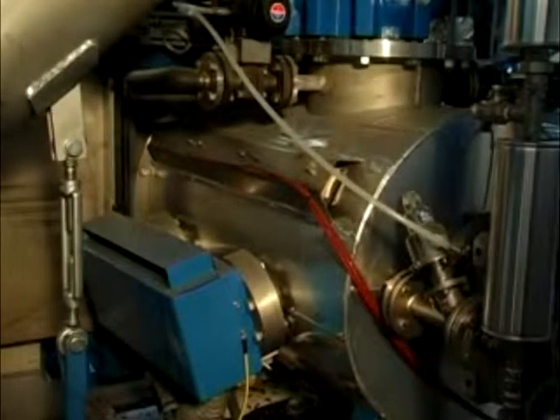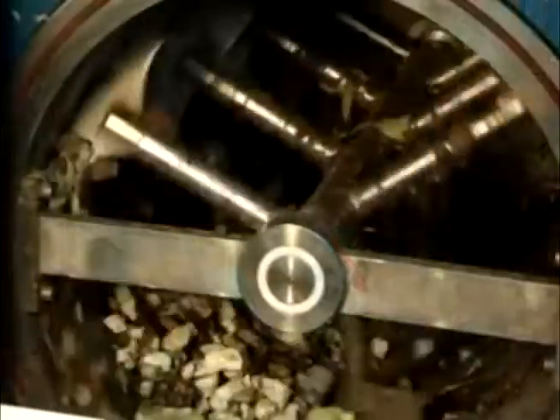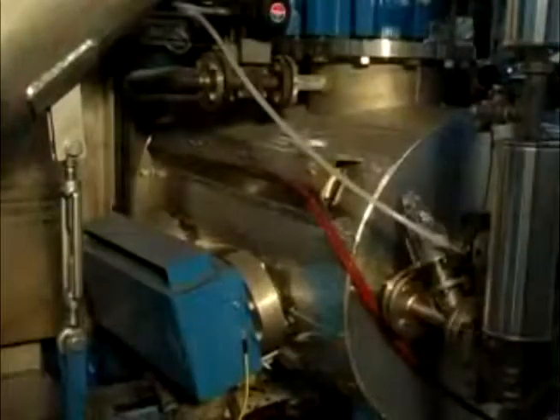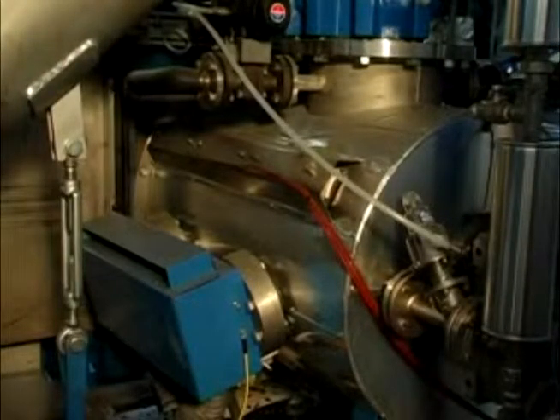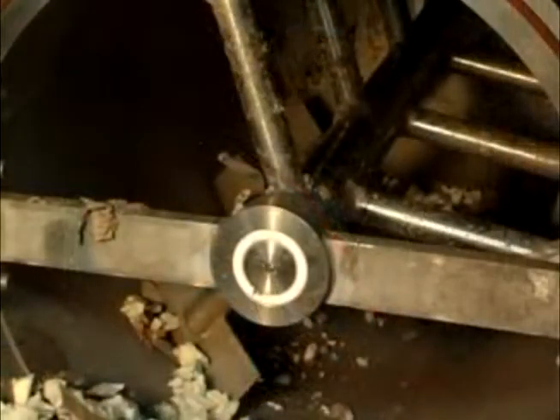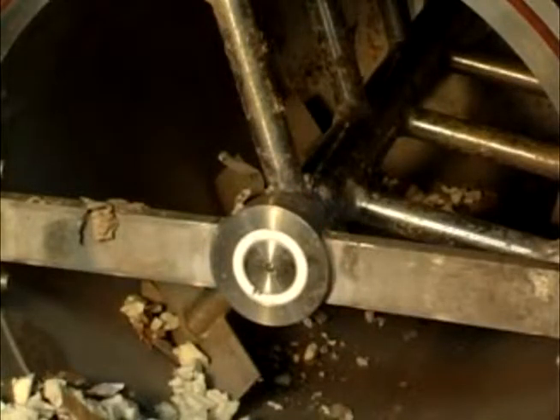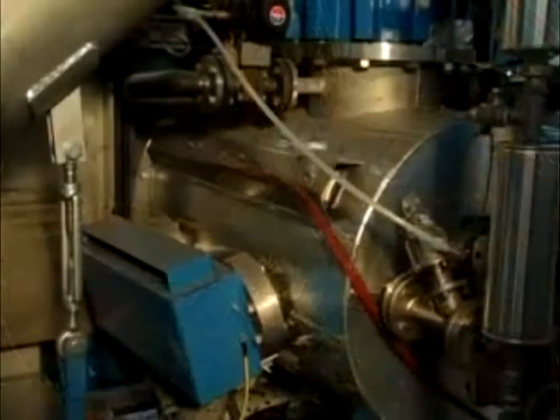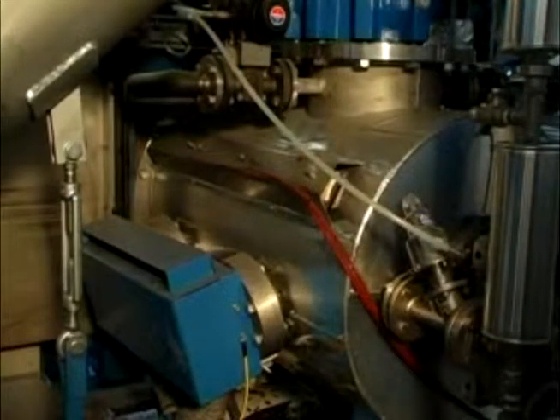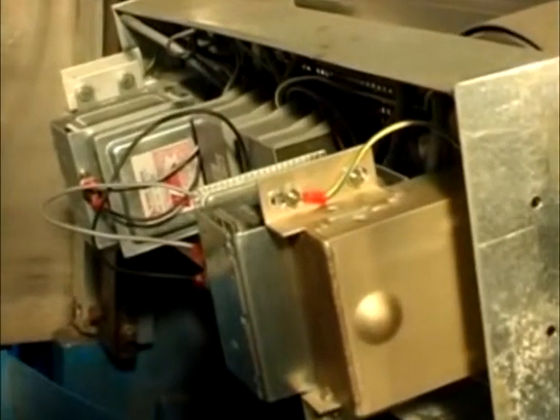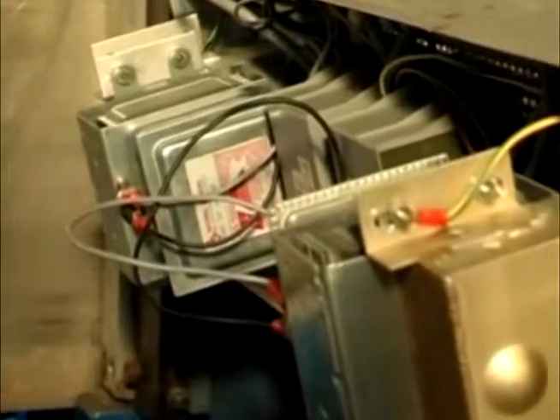The sterilization is the most important and delicate phase of the entire process. The heart of the system is a microwave chamber designed to execute the sterilization process thoroughly and safely. The cylindrical chamber where the process takes place is designed to ensure the distribution of the electric field generated by the magnetrons, which reaches all the waste fed into the machine.